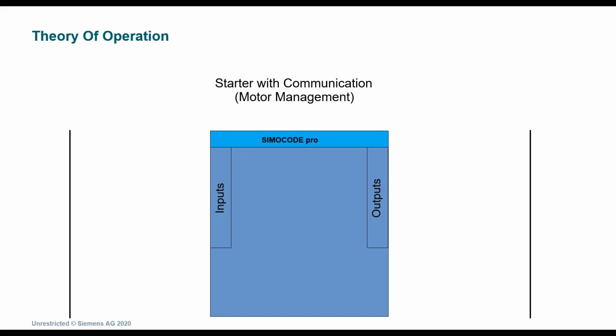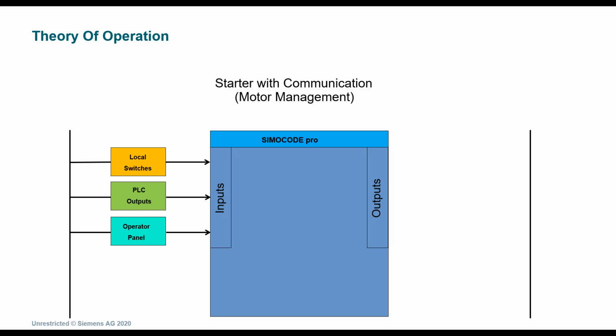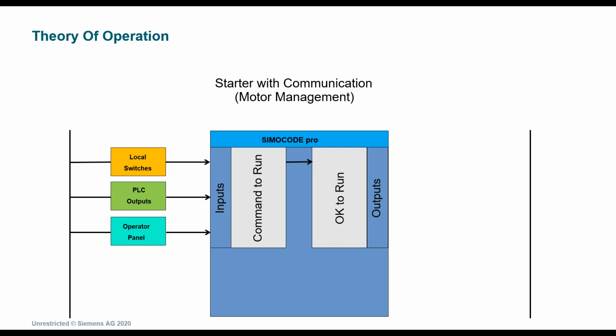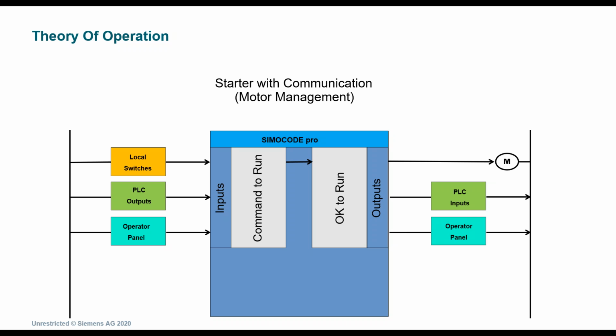Okay, starting with the communications and motor management, kind of theory of operation. We bring in all the inputs. We have a command to run, and then we are okay to run because all of our inputs, our interlocks, our permissives are in the right states. And then we turn on the motor. And we send out outputs from the SIMOCODE as an input to the PLC, and then we also send out stuff for the operator panel. This is where the SIMOCODE comes in and where it sits in the motor management for communications. But again, SIMOCODE takes over logic, it monitors, and it protects the system and the motor that it's running.